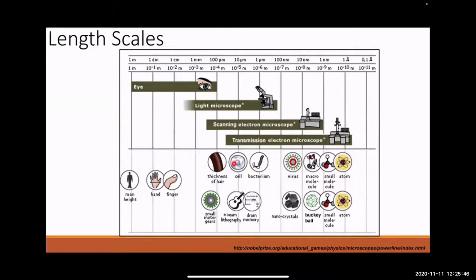But if you wanted to see structure inside the cell or features on the bacteria at a smaller length scale, light microscopy is going to come to a hard limit. And that's where EM comes in, both in the form of SEM or TEM. SEM can typically go down to about 1 nanometer. There are specialized cases where an SEM has shown full atomic resolution, but that's a very specialized case. Typically, 1 nanometer nowadays is kind of where it caps off. And then the TEM, especially with what are called aberration corrected TEMs, which is a fancy term for correcting a lens defect, an aberration, can now get down to incredible resolutions measured on the order of tens to hundreds of picometers. So fully into the length scale of an atom, so atomic resolution.